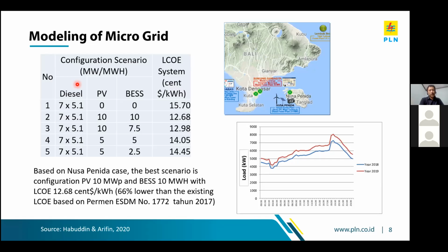For this case, we did some modeling and found that scenario number 2 is the best, because this capacity comes out with the lowest LCOE. The best configuration consists of PV 10 megawatt peak, batteries 10 megawatt hour, with the existing diesel. The LCOE can be lowered to 12.68 cents per kilowatt hour, which is lower than the existing cost by up to 66%. So this is very worth it, very useful to reduce fossil fuel use and reduce electricity production cost.